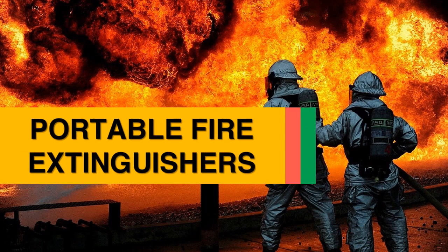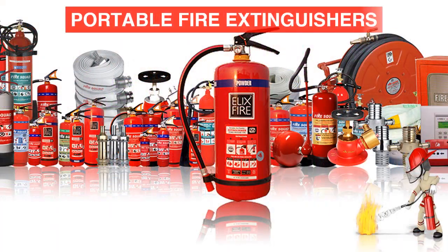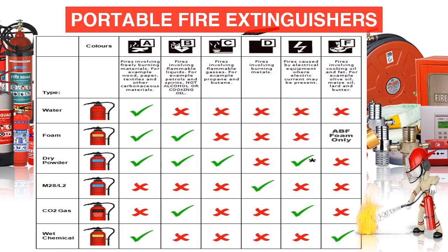The last module is portable fire extinguishers. Portable fire extinguishers are broadly divided into six categories based on application: A for freely burning materials such as wood and paper; B for flammable liquids such as petrol and spirit; C for flammable gases such as propane and butane; D for burning metals; E for electrical fires; and F for cooking oil and fat. Based on the application, different types of extinguishers can be used as represented in the matrix shown on screen.